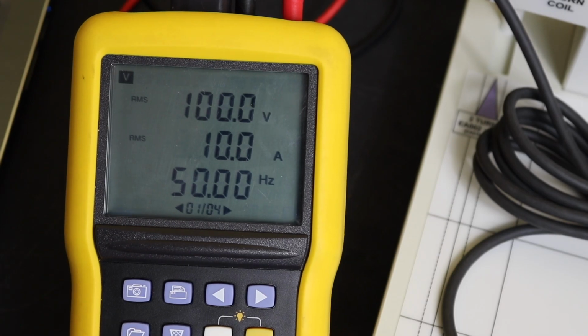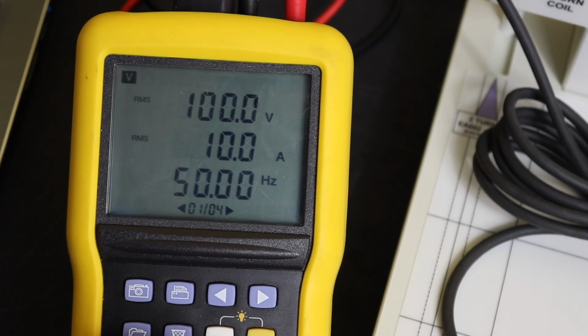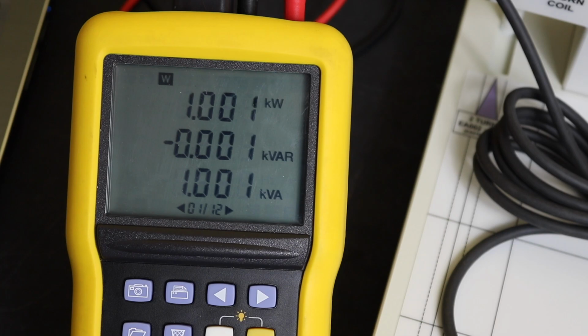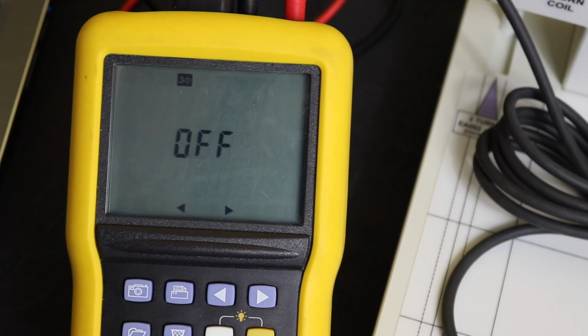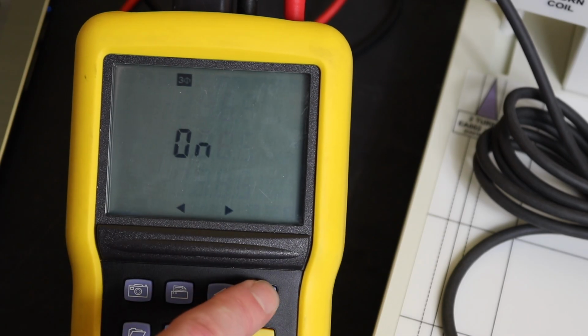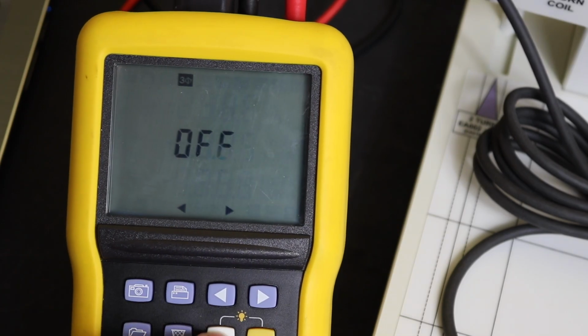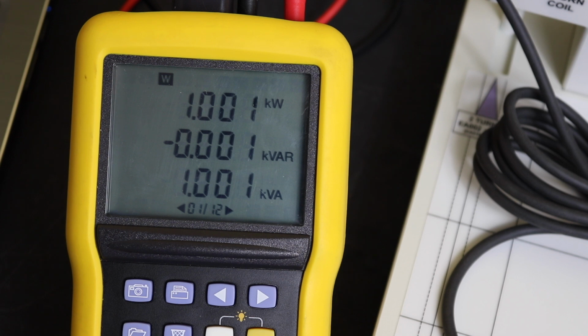Going on to the next function switch, this is power. So you can have power either 3-phase or single phase. It defaults to single phase. To get to 3-phase power, we go onto the yellow button, and then we select it there, on or off. Obviously I've only got a single phase injection test set, so that's all we can do at the moment.